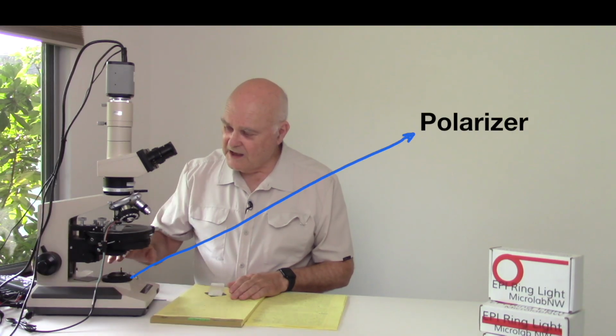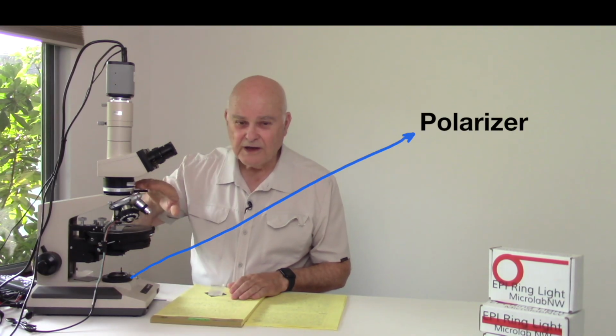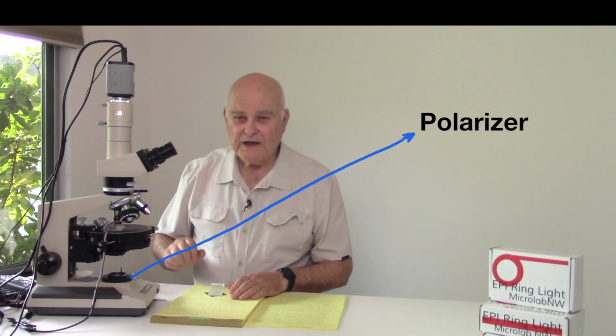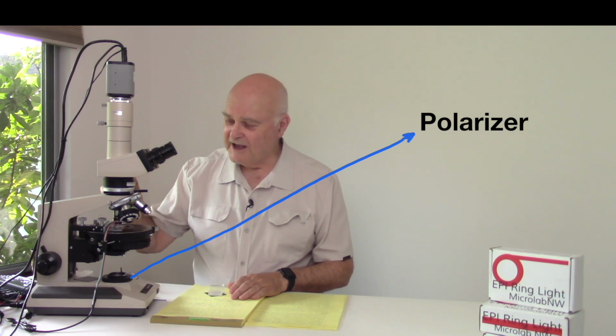In the microscope, that's done by having a polarizing filter on the base of the scope, and then there is a built-in polarizing filter in the polarizing intermediate tube that is always present in a polarized light microscope. The polarizing filter at the bottom of the scope is referred to as the polarizer. And the polarizing filter in the polarizing intermediate tube is referred to as the analyzer.